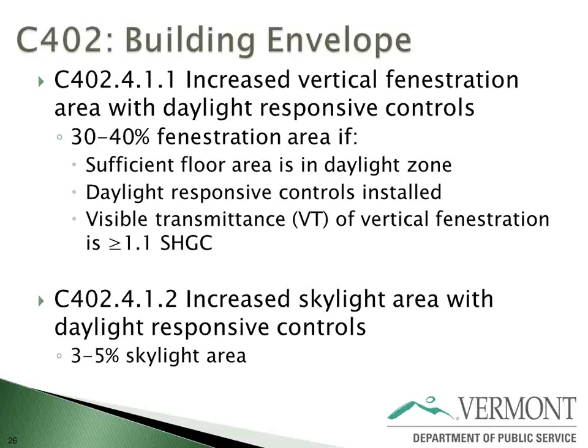The same applies to skylights. Skylights are capped at 3% area, and you're allowed to go up to 5% with similar criteria as listed above, daylight responsive controls, and you can increase your skylight area up to that stated maximum.